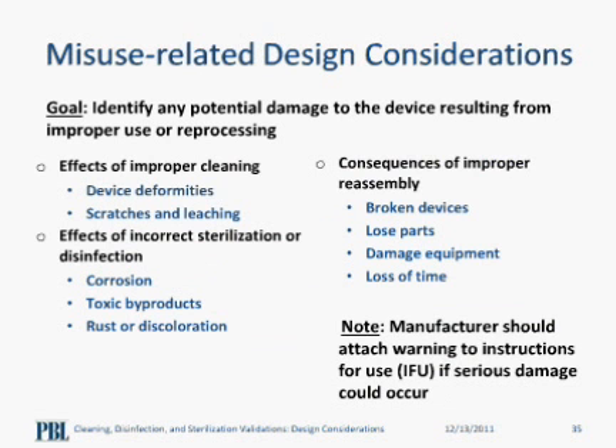In order to prevent any harmful effect, manufacturers should include a warning in the instructions for use, especially if it is known that serious damage could occur related to device misuse. A good example of this is accidental immersion of powered equipment or devices. Not only does it affect the functionality of the device, but it poses great danger to users as well.